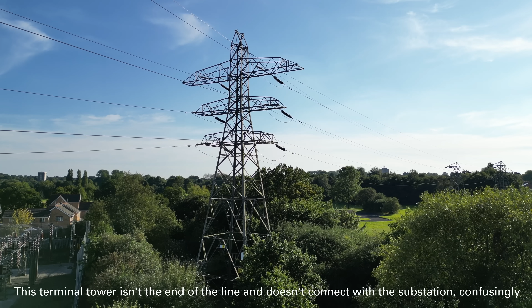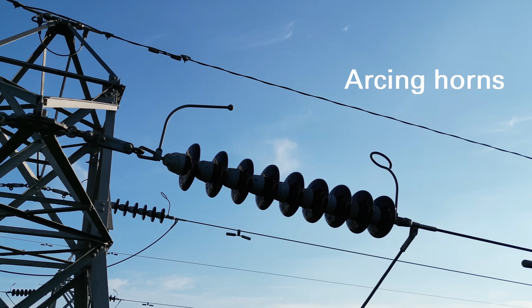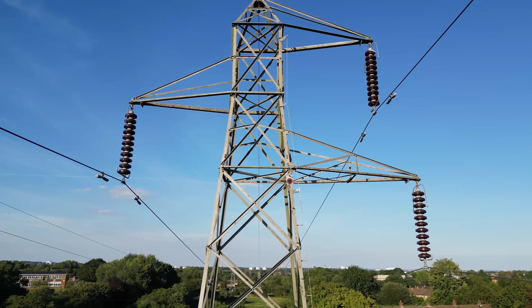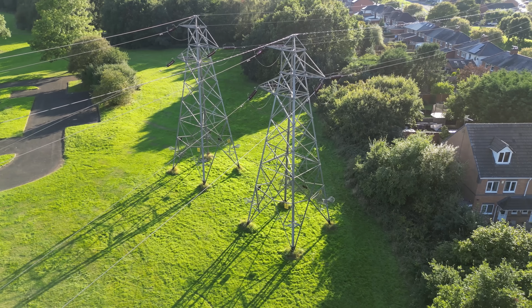The biggest, terminal towers, are at the ends of the line. Looking again at the insulators, at the ends you can see arcing horns pointing towards each other. If, for example, lightning strikes a power line, the extremely high voltage can flash over the insulators, potentially causing a sustained arc which would destroy them. The shape of the arcing horns makes any arc blow itself out. For protection against lightning, power lines also have at least one ground wire at the top, which helps to shield the conductors. You can also see Stockbridge dampers, a type of tuned mass damper. This is to prevent resonance building up in the cables in wind.